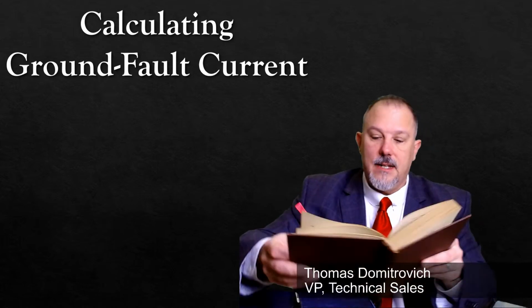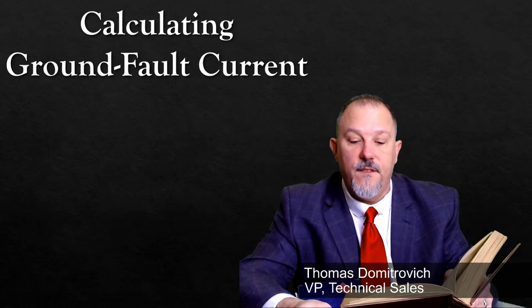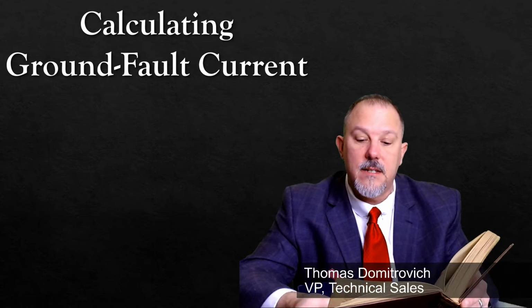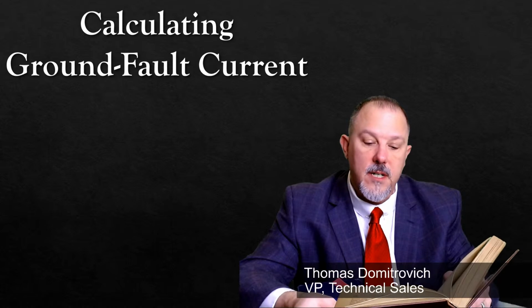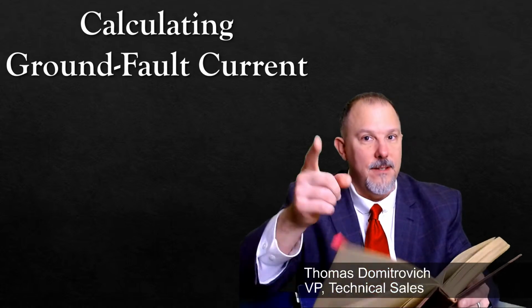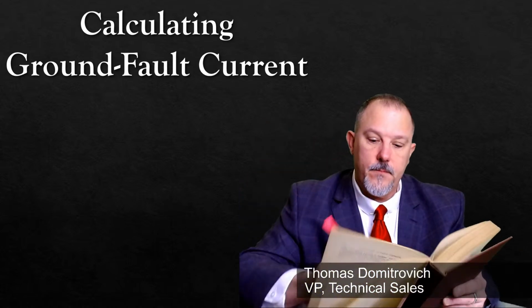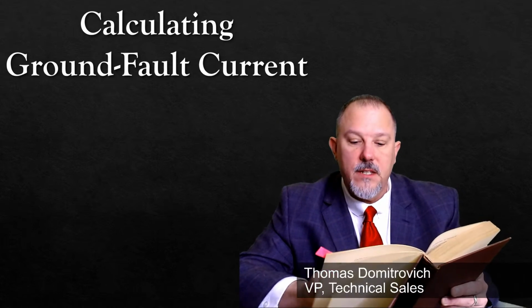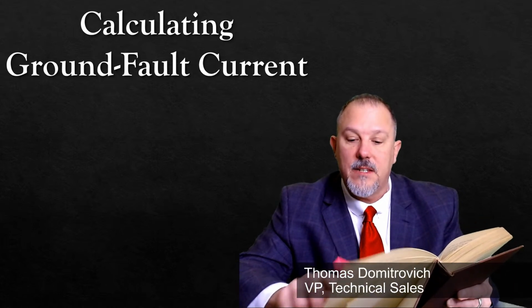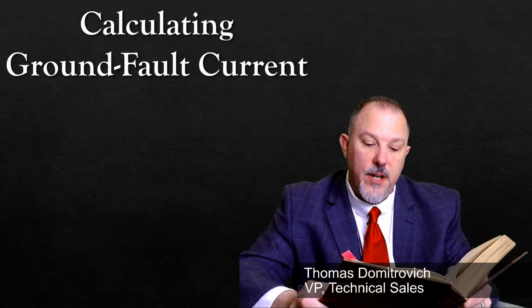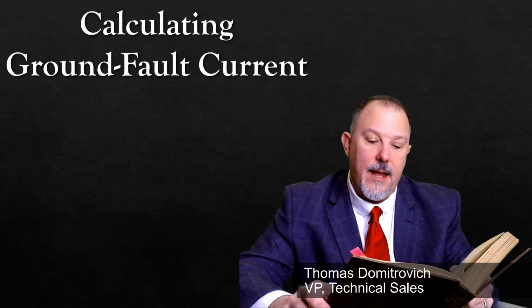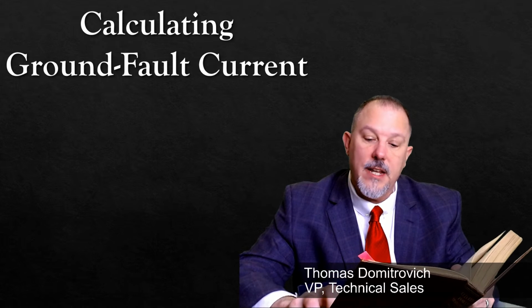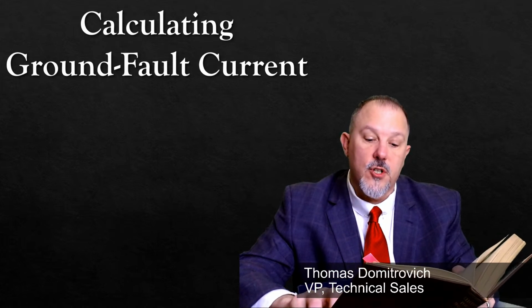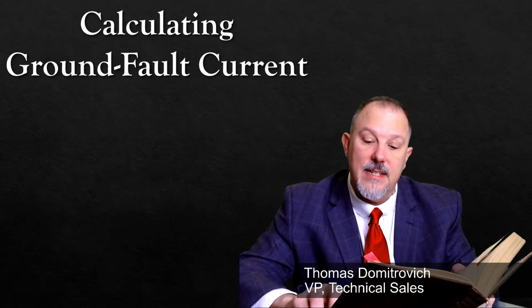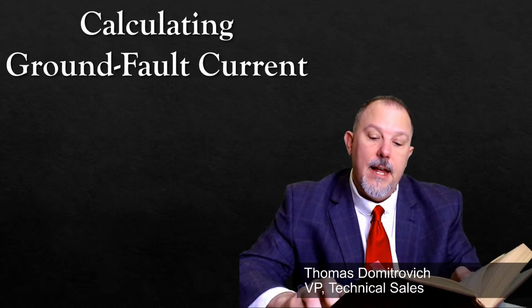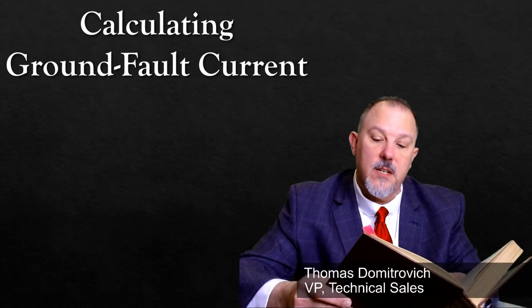It says that in symmetrical components, the great majority of faults on power systems are of an unsymmetrical nature, the most common type being a short circuit from line to ground. That's what we're talking about right there. The system impedances are usually symmetrical throughout its main elements: generators, transformers, transmission lines, etc., and the load. The fault currents, usually unsymmetrical in three phases, may be resolved into positive, negative, and zero phase sequence currents. And the magnitudes of those are based upon the impedances in there.